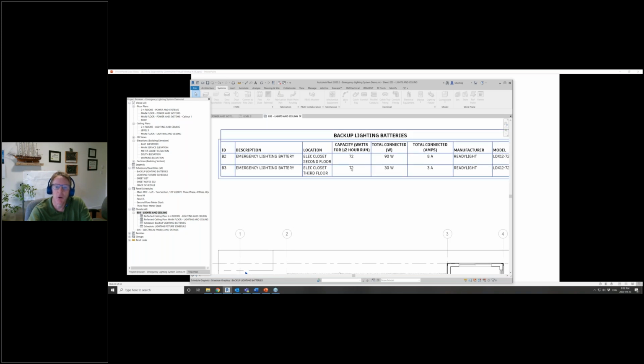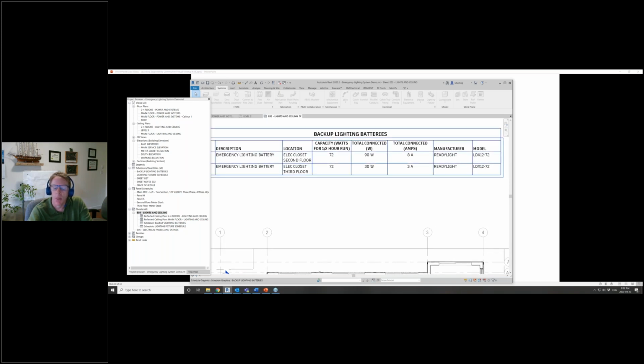It has a 72-watt capacity for a half-hour run, so that's a parameter in the part. Revit is telling us that our total connected load is 30 watts. Each of those remote heads we just connected has two 5-watt LED heads, so a total of 30 watts. Total amps connected is 3 amps.